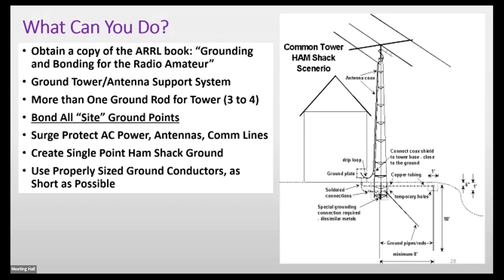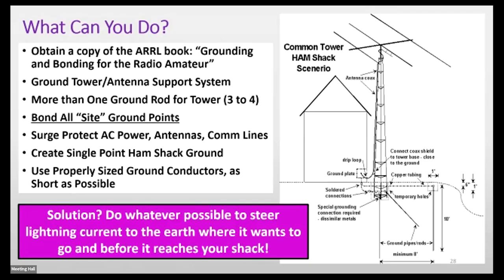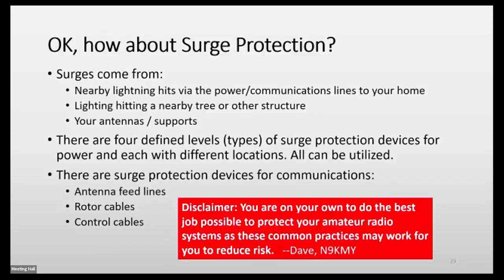Ground the antenna support and ground rods, and bond the site ground points. Protect the AC power with surge protection. Create a single point ground to the shack and properly size the ground conductors as short as possible. Whatever you do, steer that lightning to earth. That's what you're trying to accomplish. Now, how about surge protection? Surge can come in different ways and places besides what we've talked about: through your antenna feed lines, rotor cables, control cables, power, you name it.